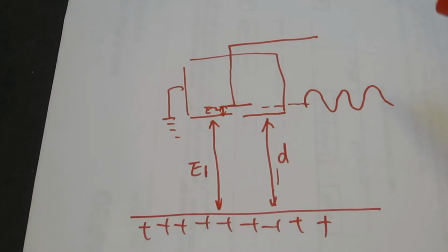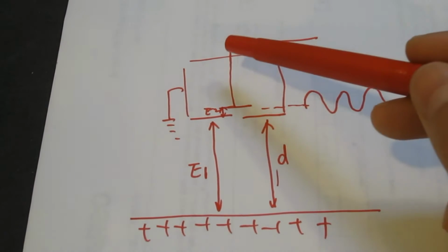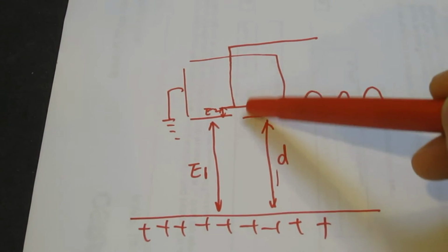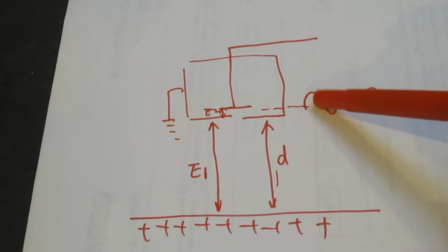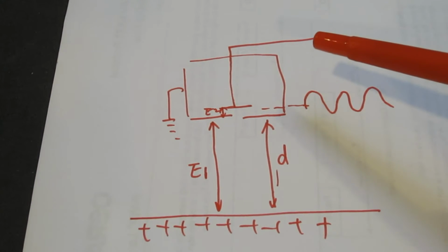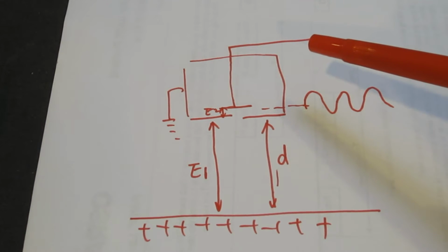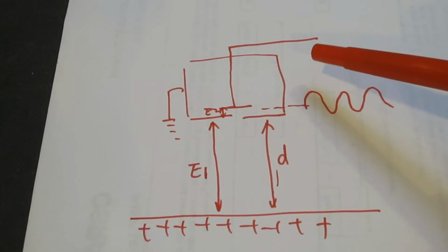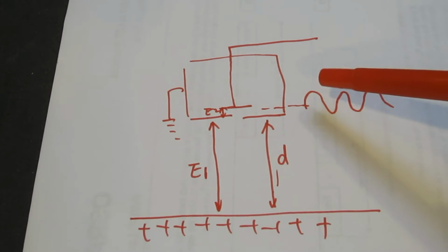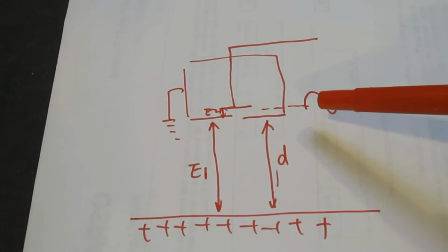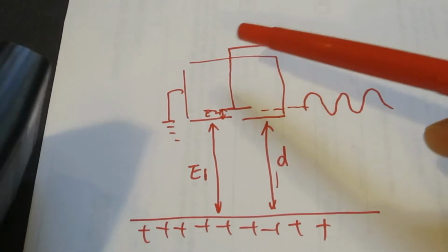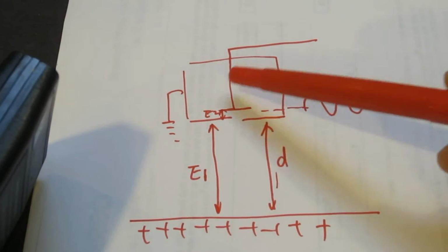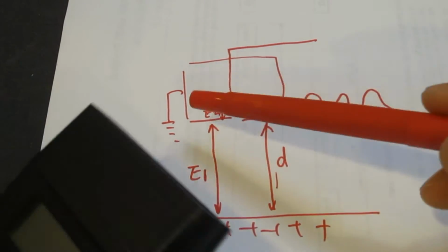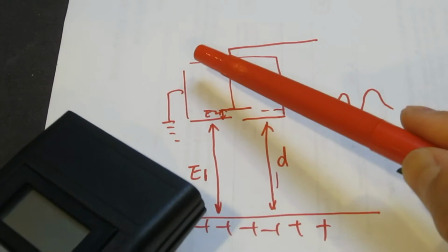By the way, in some literature, the second type of sensor, the one where the plate oscillates in a sinusoidal fashion, is sometimes called a Kelvin vibrating capacitor sensor. You can take a deeper look if you're interested in that. But I think ours, as I mentioned earlier, is the first kind. This is a fixed one. That's why it has a dependency on the distance between the head of your measuring device and the material being measured.